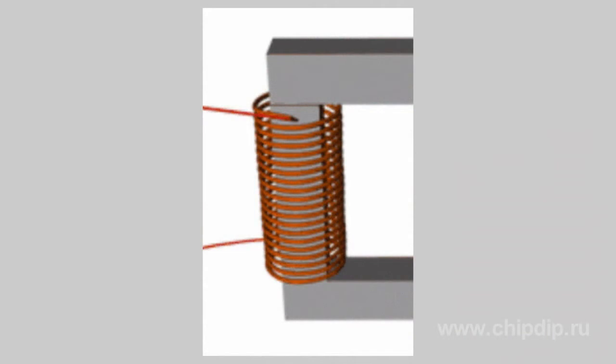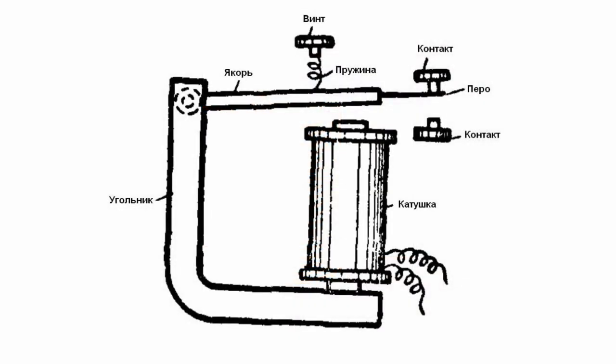Winding is made of enameled copper wire. A bobbin is put in a circular core made of soft annealed iron and screwed into an angle joint. At the end of the angle joint, an axis of thin laminated armature having a pen point moves from one contact to another while operating. An external screw adjusts the tension on a coil spring working on the anchor.